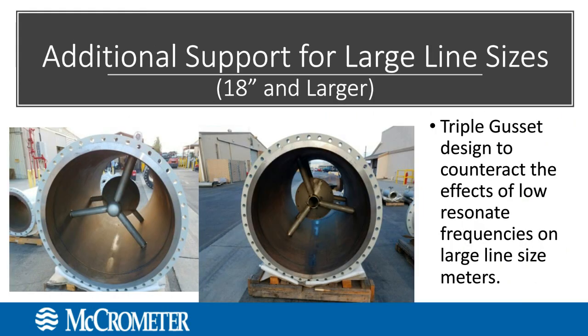The VCone can be created in a number of large line sizes. And now what we had found, and a new novel design that we've been working on lately, has been additional support for our large line sizes, specifically looking in the 18-inch and larger range. We've added a triple gusset design that counteracts the effects of the low resonant frequencies, meaning that for larger meters, the frequency can be low and cause the cone inside to vibrate. Now, in order to stop that from happening, we've added this design over here, which adds an additional amount of bracing and support to counteract the effects of vibration.